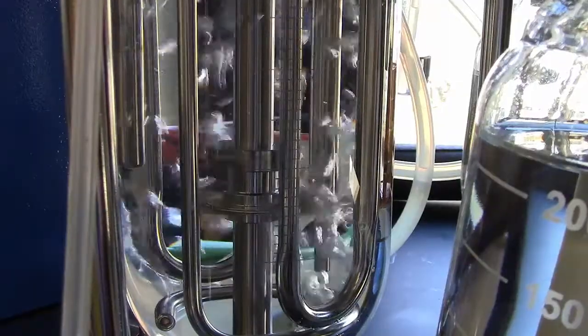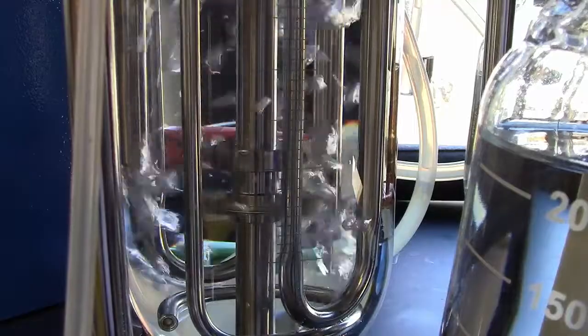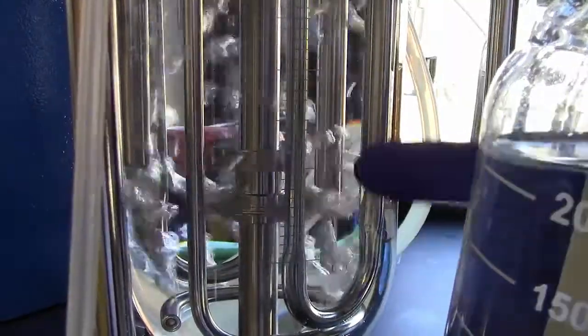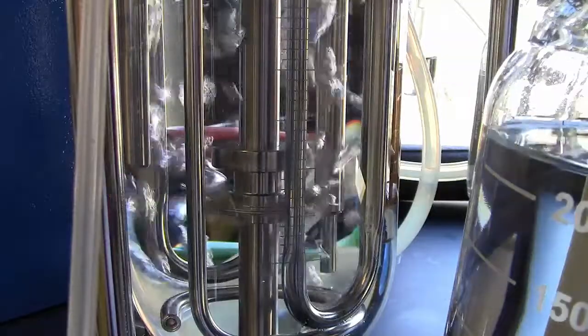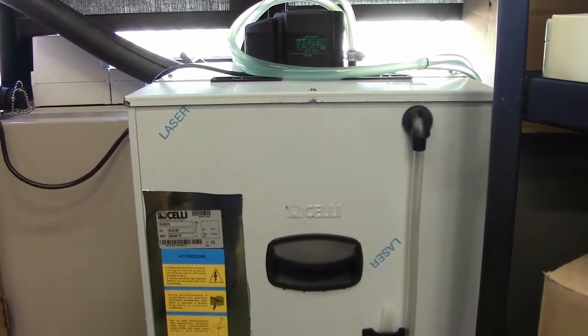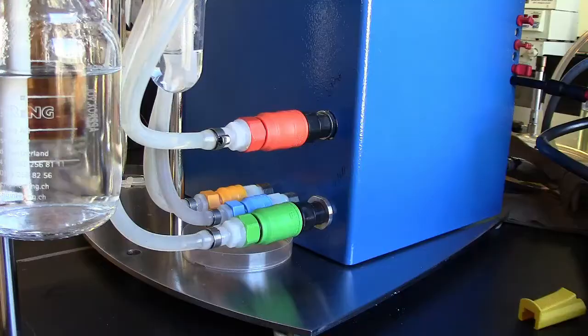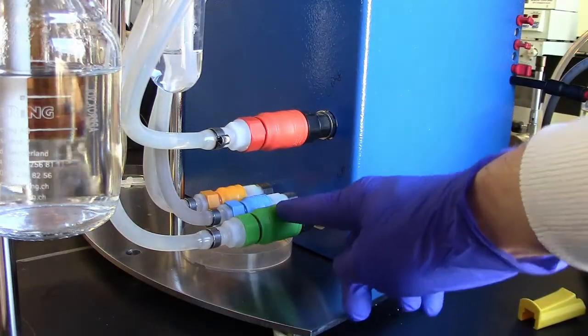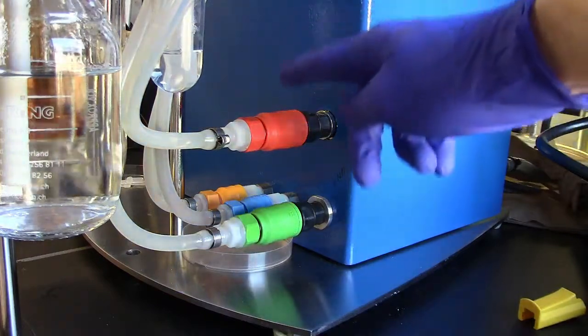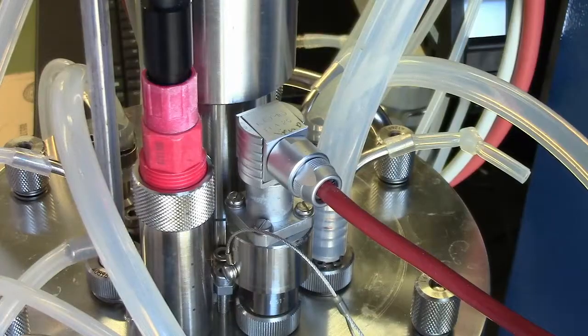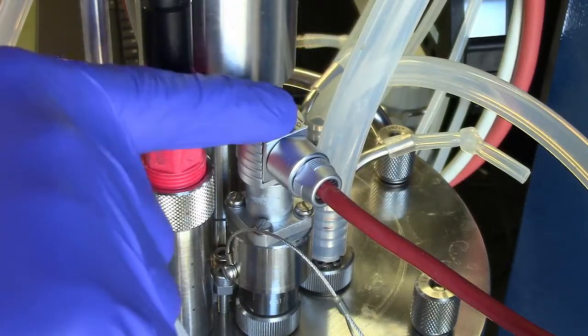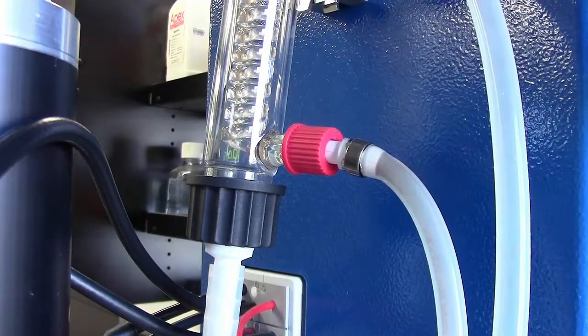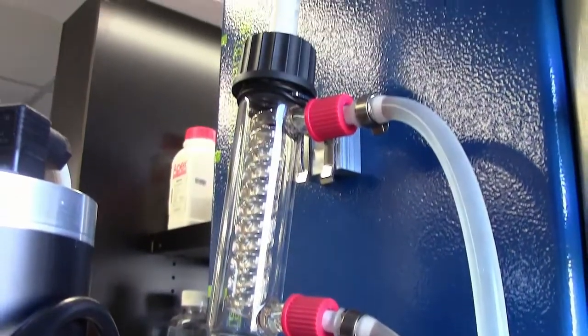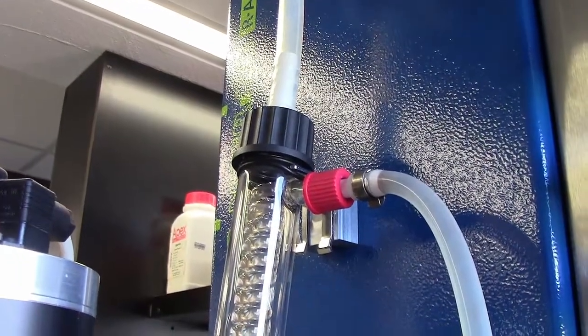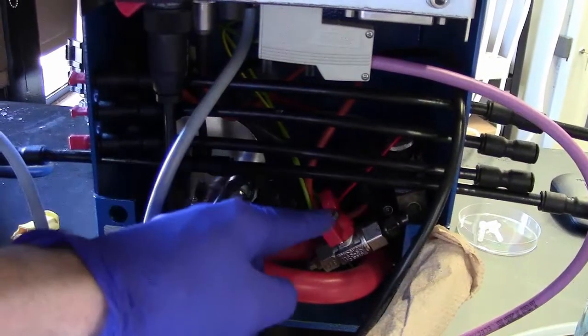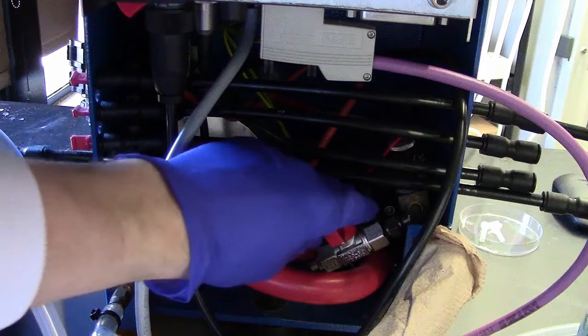Temperature control. The temperature of the fermentation is controlled by water circulating separately from the culture media through a series of pipes running through the vessel. Water is supplied to the fermenter from the chiller, which connects to the back of the control unit. This water flows from the green port on the tower to the baffling within the vessel and returns via the orange port. During operation, the temperature probe in the vessel controls the flow of water through these pipes. Above the fermentation vessel, the reflux cooler is equipped with a condensing coil to reduce media volume loss due to evaporation. Flow of water to the reflux cooler is controlled by a valve at the rear of the machine.